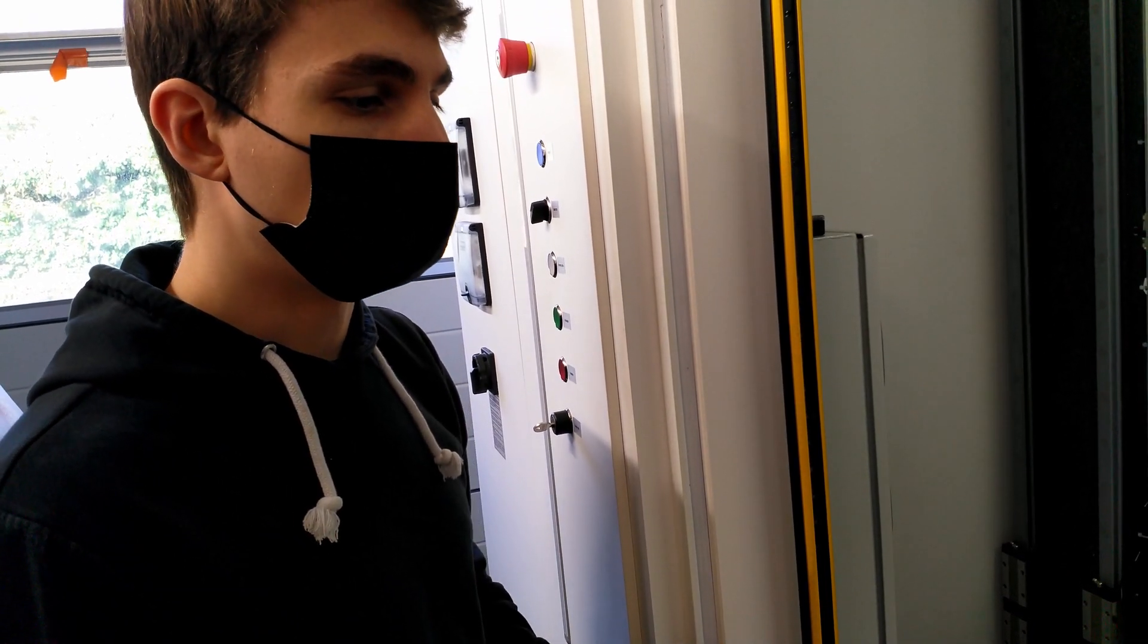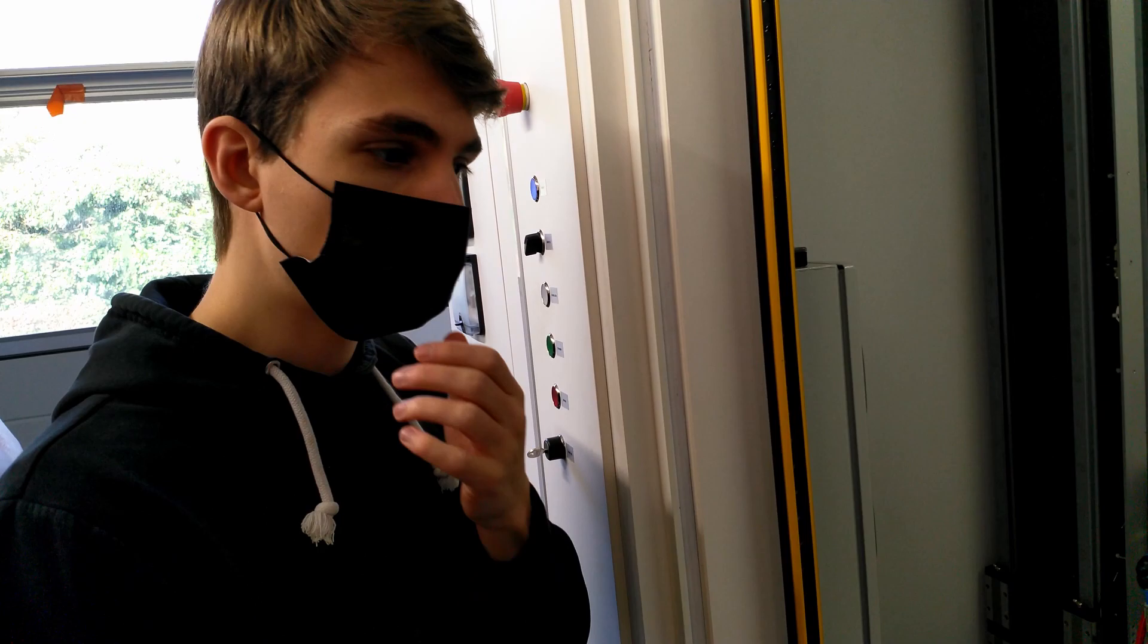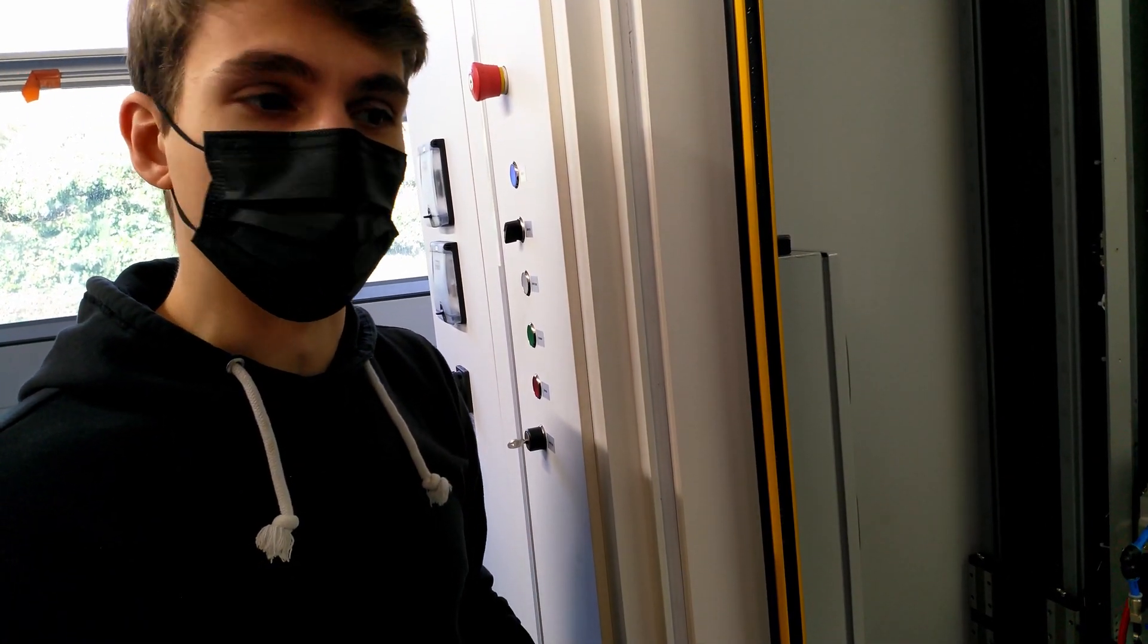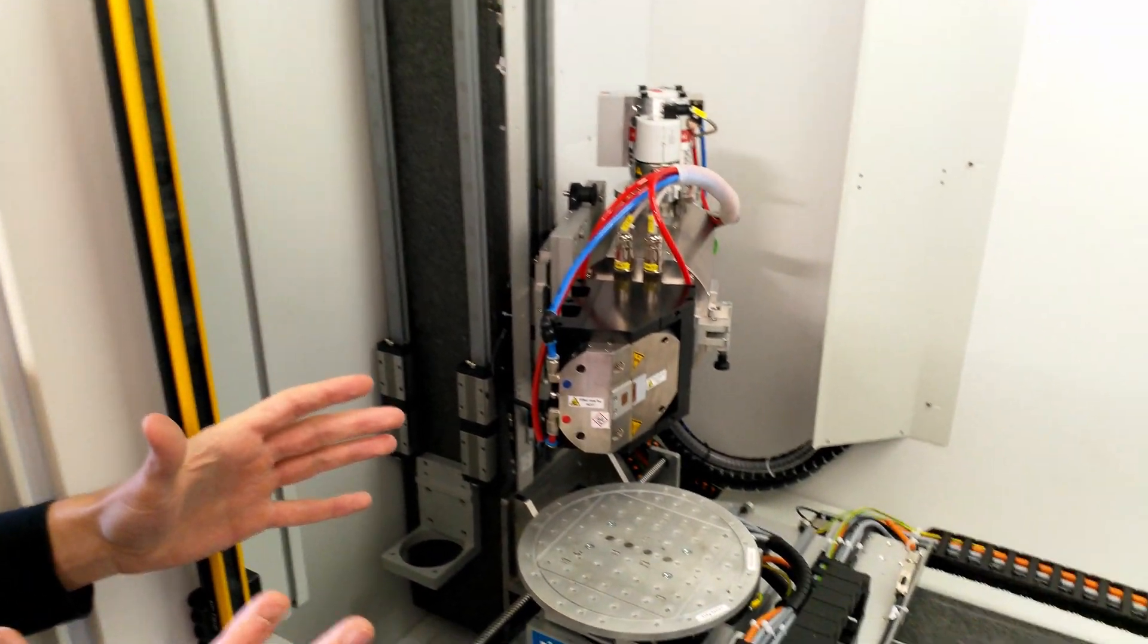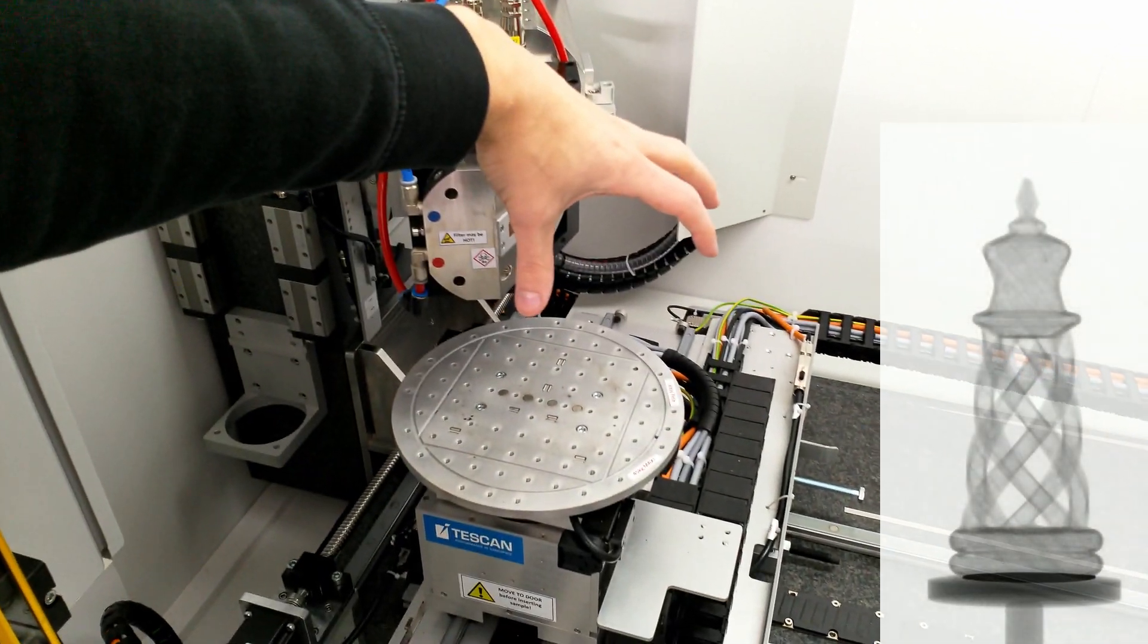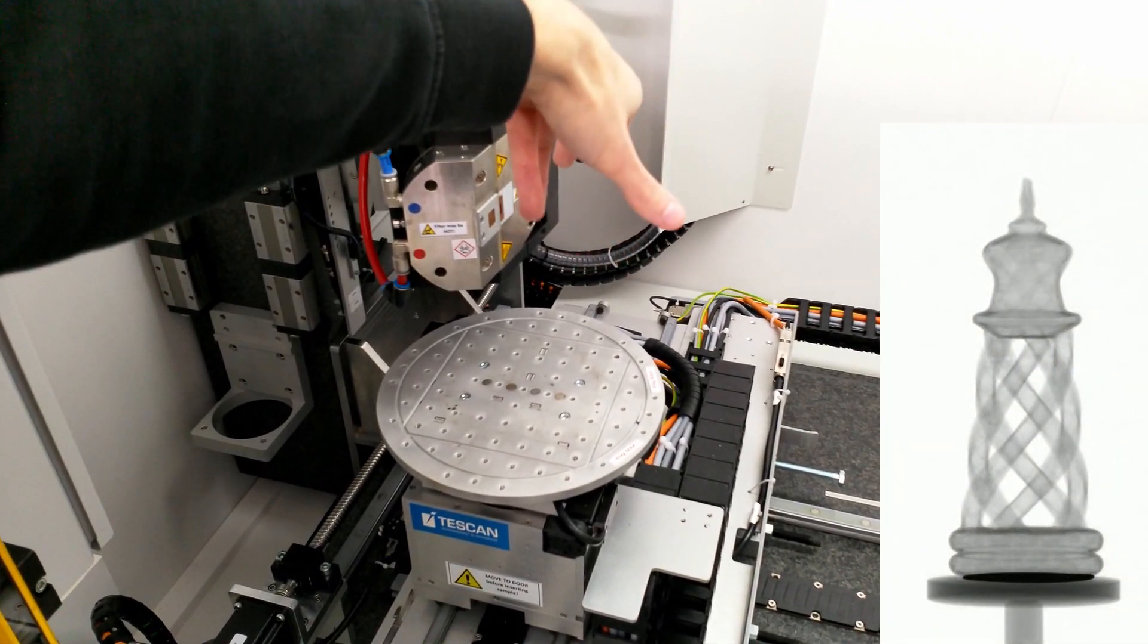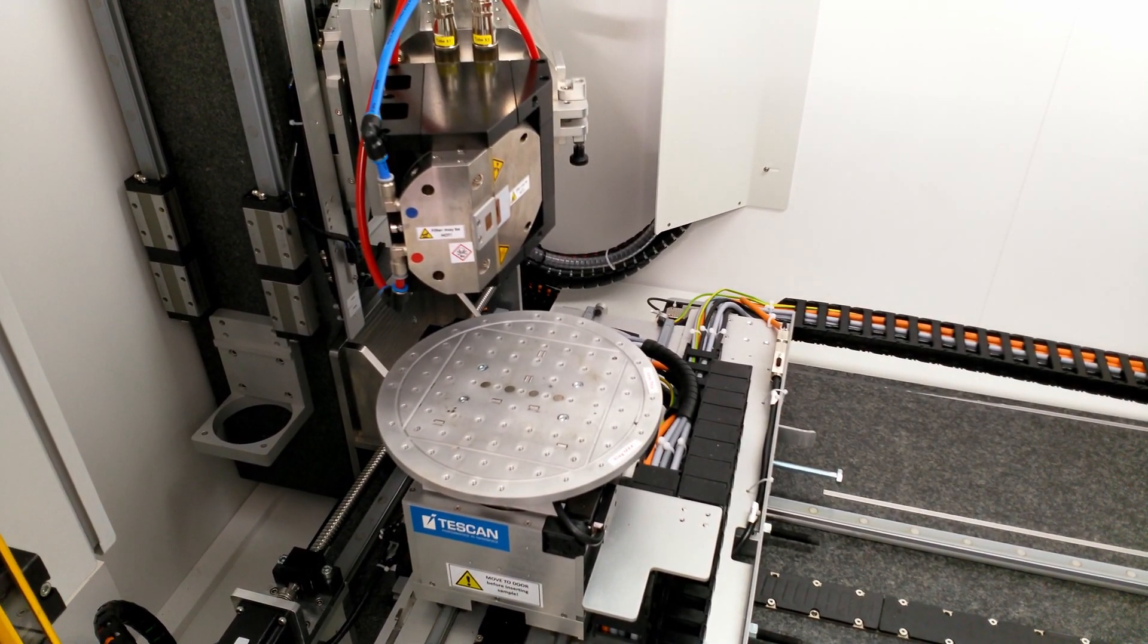Such an x-ray shadow is exactly the same as an x-ray radiograph you get at the hospital when you break a bone, but this is not yet a CT scan. The CT scan makes such a projection at many angles, which is why we have the rotation stage. We rotate the object and take a projection at many angles, and then we use mathematical algorithms to reconstruct a 3D image from that.